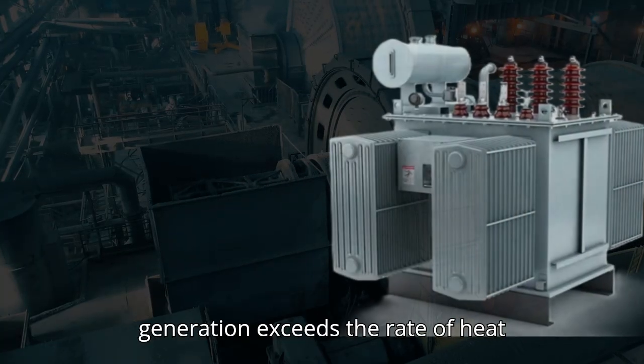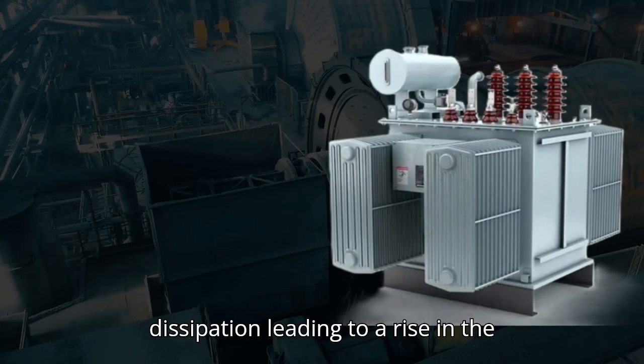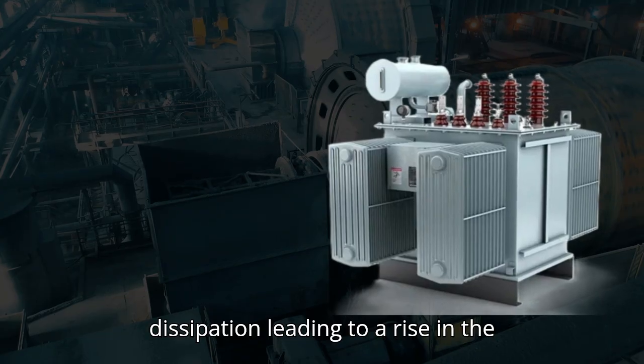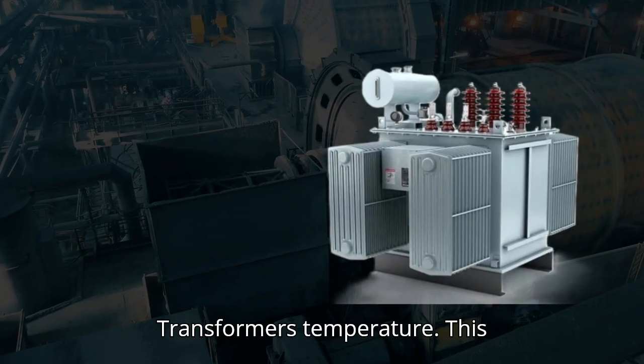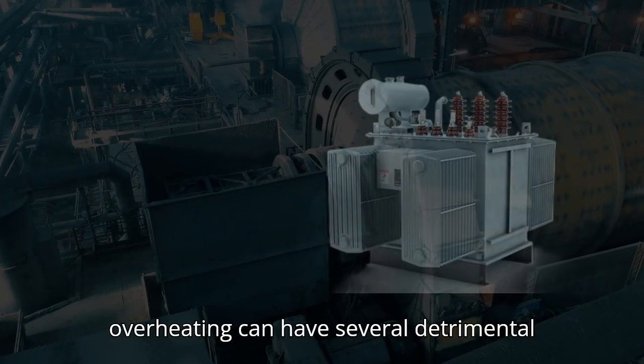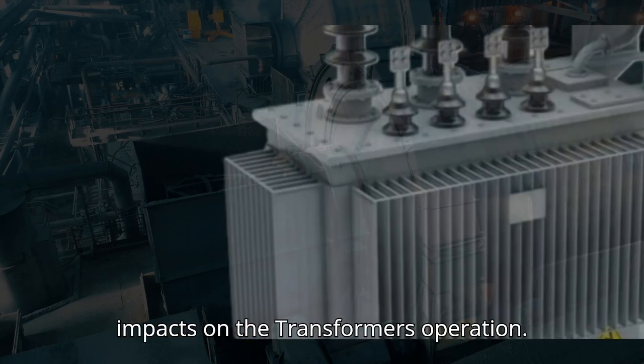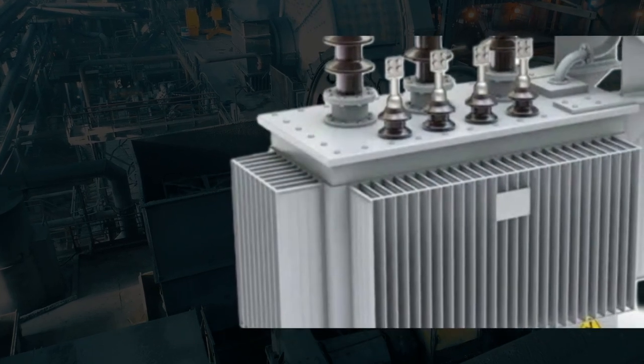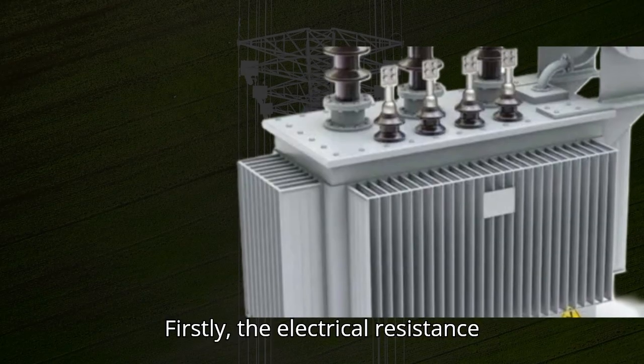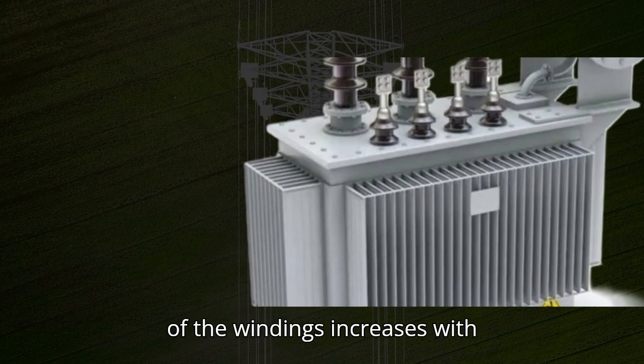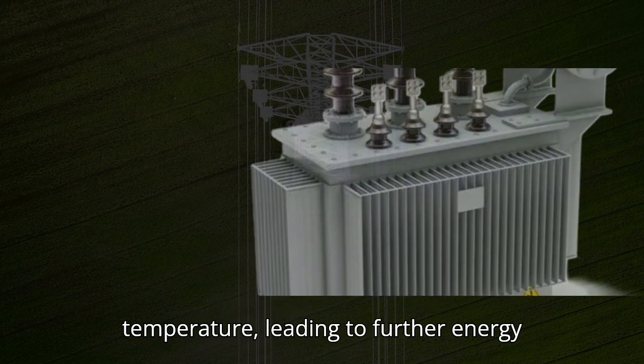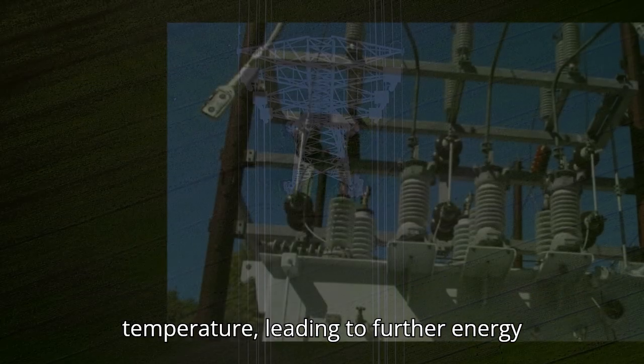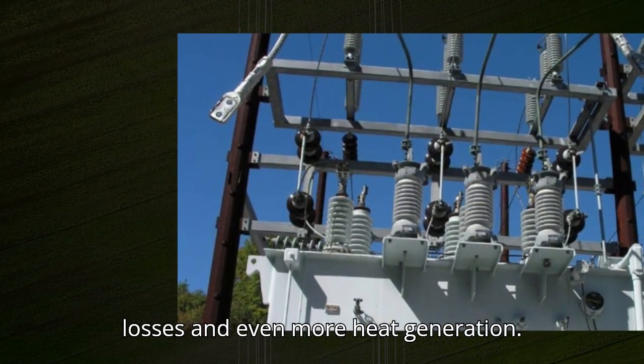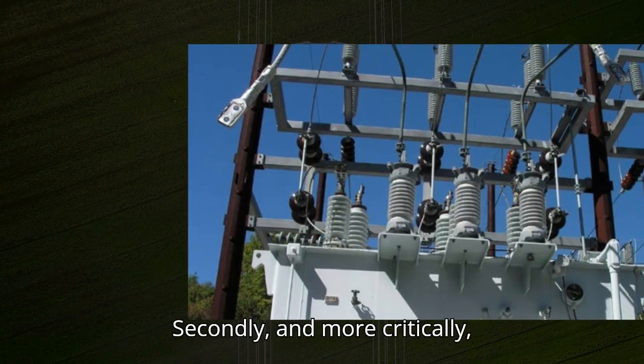However, during an overload, the rate of heat generation exceeds the rate of heat dissipation, leading to a rise in the transformer's temperature. This overheating can have several detrimental impacts on the transformer's operation. Firstly, the electrical resistance of the windings increases with temperature, leading to further energy losses and even more heat generation.